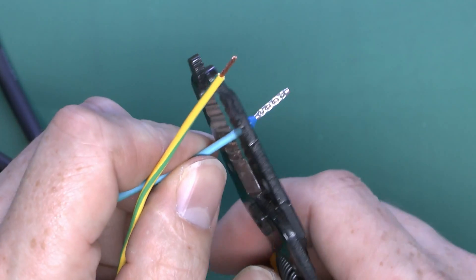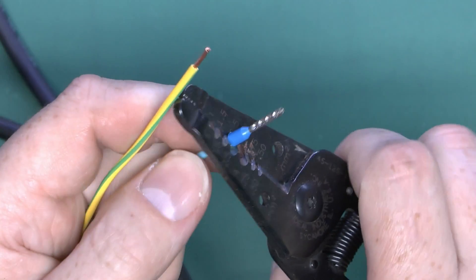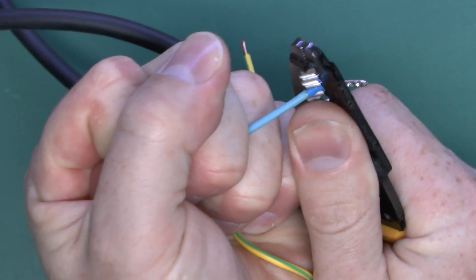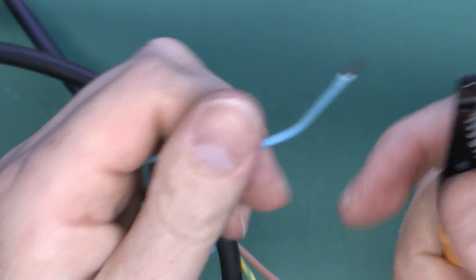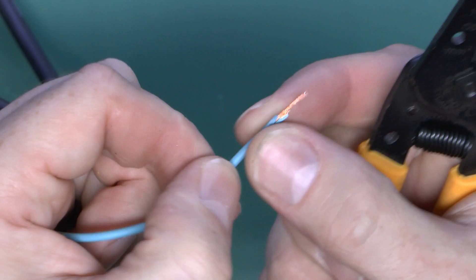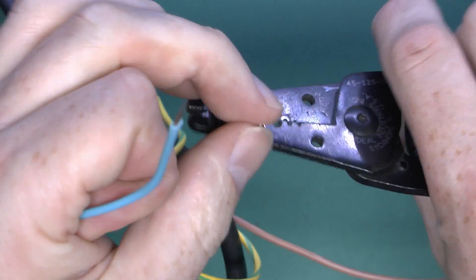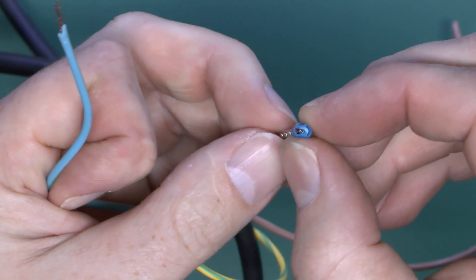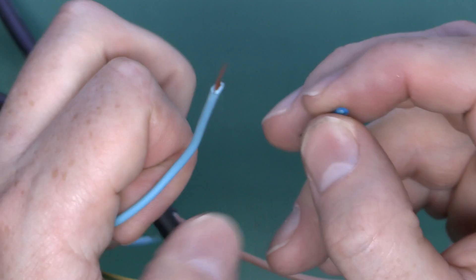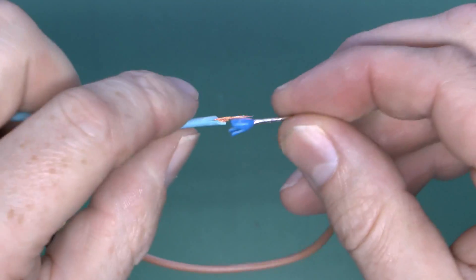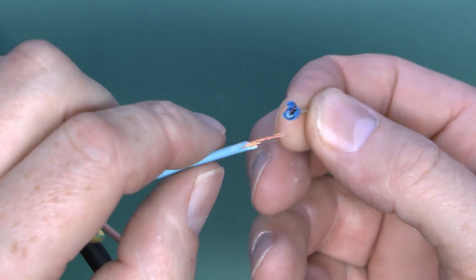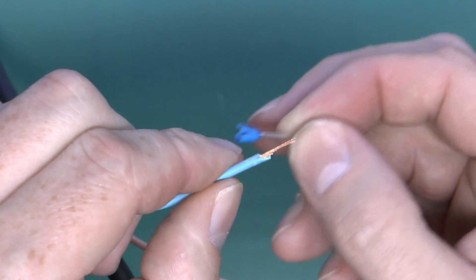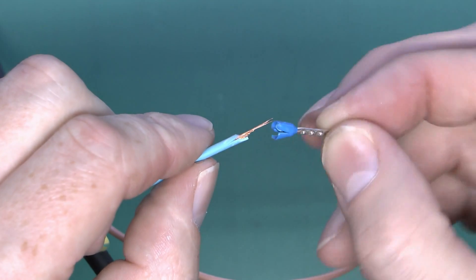And let's just see if we can actually remove it from here. Just place it in this stripper. And it's the only way we can actually remove it we've actually basically ripped half of the wire off of the end. The actual terminal itself still has a fair amount of the wire inside and so we've actually broken the bottom out completely. So done properly these are things that are not going to just fall off. You've basically got to destroy the thing to actually get it open and so we've actually just ripped through the copper strands there and completely broken and destroyed it.